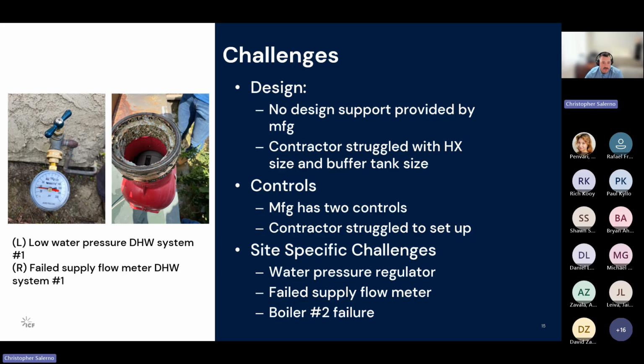And then lastly, obviously, was the boiler failure. So there were several things that arose during this project that resulted in delays, and things that need to be considered in the future to be able to prevent these, such as building bypasses for these pipings. So if, say, a flow meter does fail, you can just have it on a bypass, and then you can close off the bypass and essentially swap these meters in and out, because they're threaded by unions, and once the piping is installed, swapping them in and out is not difficult. It's not very complicated, and it's doable.